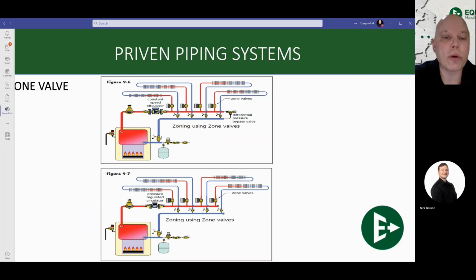If you only have one of those zone valves calling, then the rest of them are going to be closed, which means you're going to have a whole lot of flow going through just that one zone, which means that you need to install what's called a differential pressure bypass, which is going to be collecting all that additional flow and sending that back into the return.